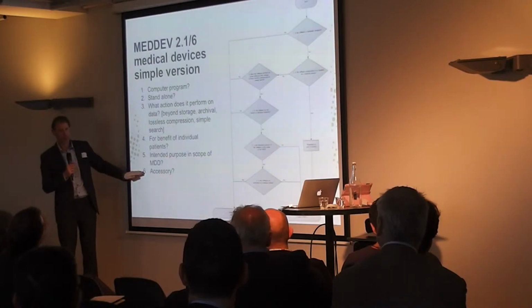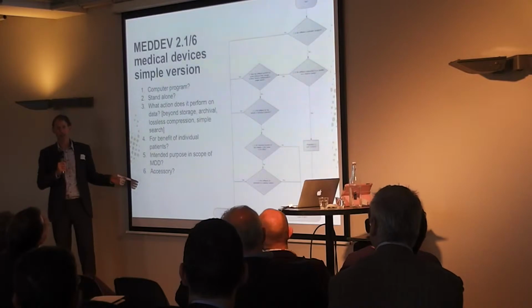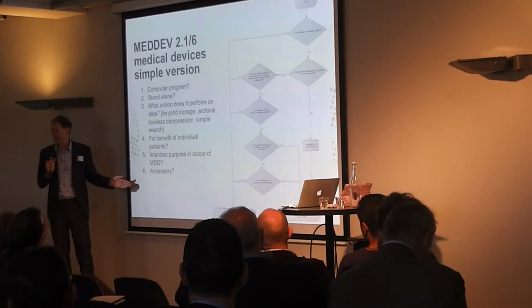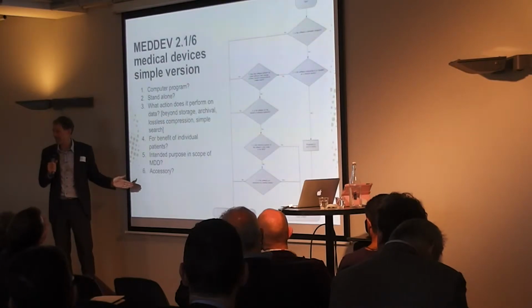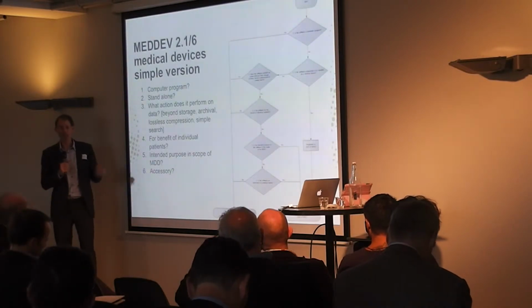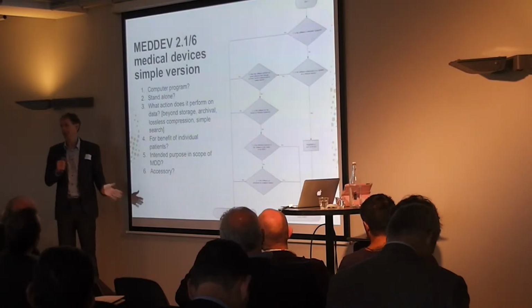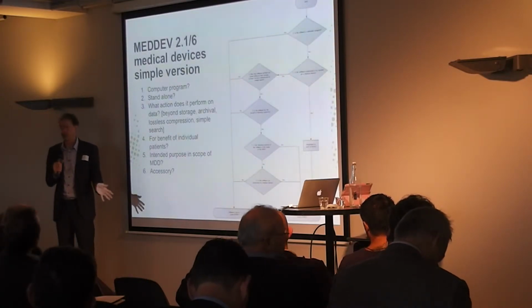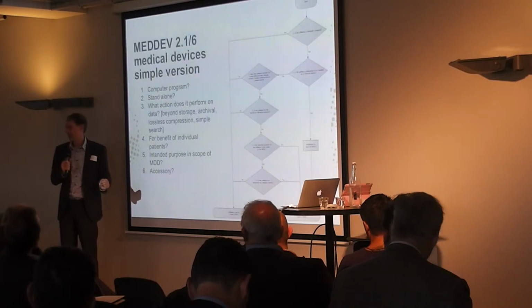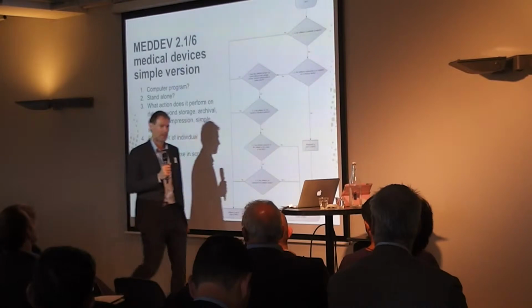So really think about this. I point out accessories because the medical devices regulation proposes a definition of accessory that is much wider than the current one. The current definition is that an accessory is anything that enables a medical device to achieve its intended purpose. The new definition is "enable or assist." Well, what's "assist"? That can be really broad. So good luck with that.